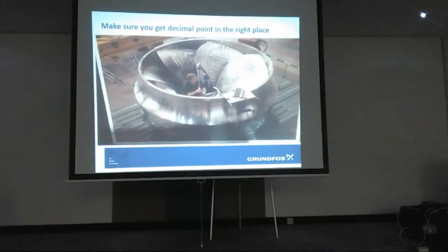We should all be working to SI, because those mistakes happen in lots of systems, and people are continuously using cubic metres an hour, and that's not the right figure. I thought it was cubic metres per hour. Oh, it would be for water, yes. I was water gallons a minute. But the problem there is if you're using metres or litres an hour, you are going around with 3,600, and that's a silly game, because you're really just going back to the difficulties of imperial systems. I'm sadly old enough, and I still could design a gravity system. Would you? Oh yes. It's an annoying thing because people do make mistakes. Everybody's in a rush anyway nowadays. Absolutely. You want to try working it out longhand now and again, and you'll suddenly realise where you went wrong. But when the computer says that's the answer, that's it. Don't go back and work it out.